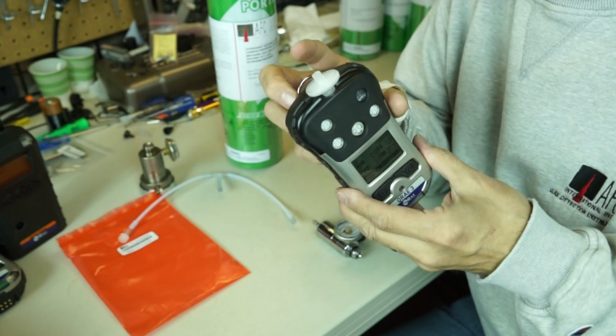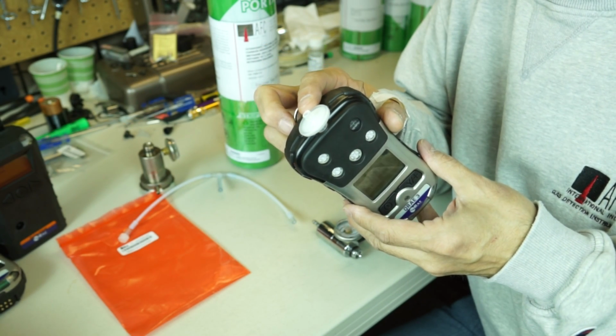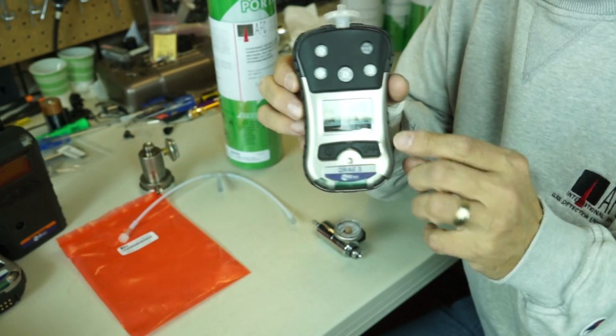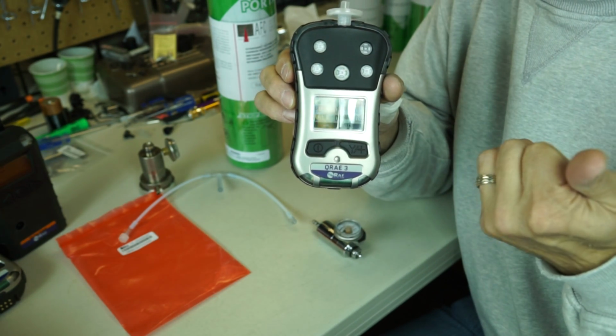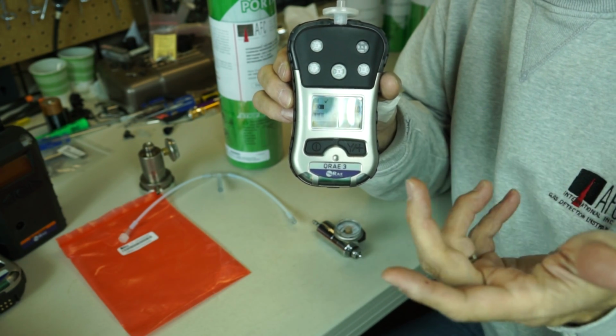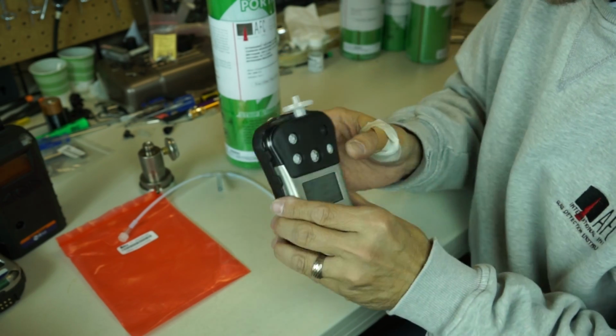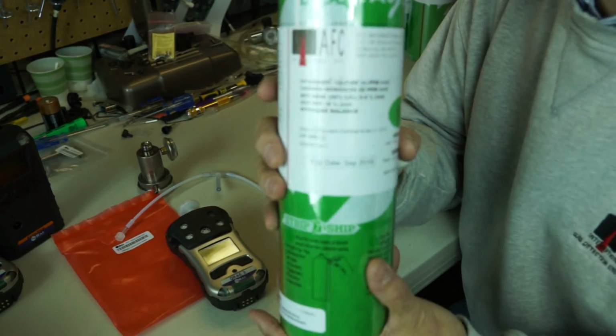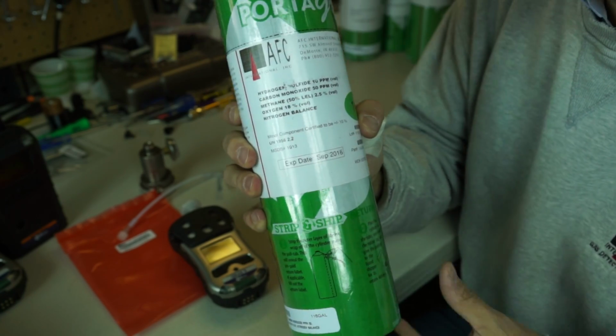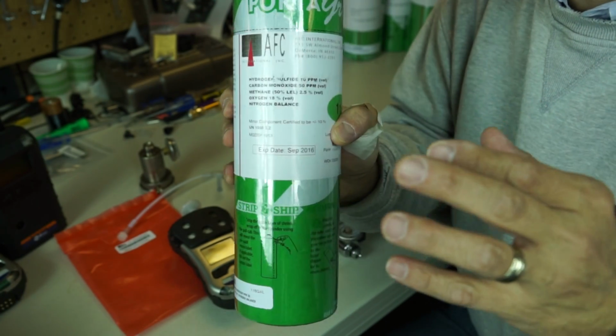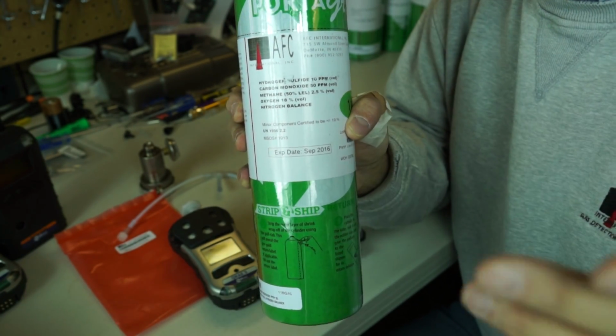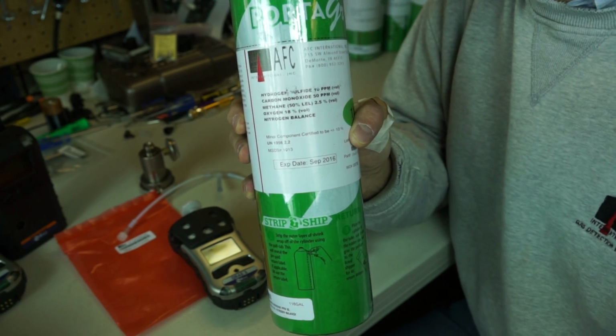So the QRae 3 has the filter and the pump inlet right at the top of the unit. This happens to be a 4-gas instrument: LEL, oxygen, carbon monoxide, H2S. Okay, so the first thing you're going to do is make sure that you have the proper gas mix. Now, a lot of people will say, well, do I need to use the manufacturer's gas? Well, out of courtesy, we like to use the manufacturer's gas whenever possible, right?